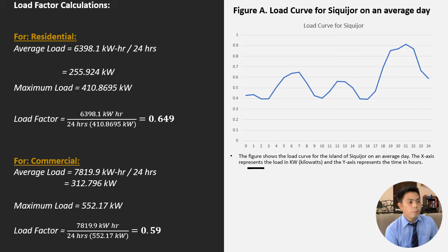For the commercial calculation, the average load is 7,819.9 divided by 24 hours, equal to 312.796 kilowatts. The maximum load for a commercial building is 552.17 kilowatts. To get the load factor, you divide the average load by the maximum load, which is equal to 0.59.